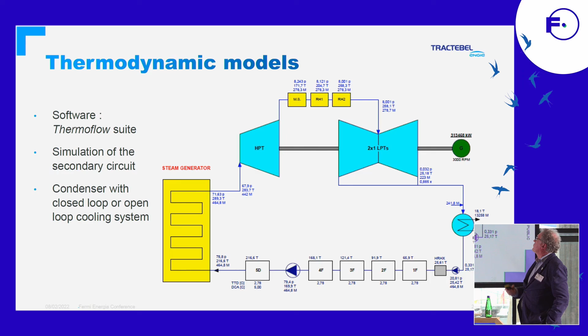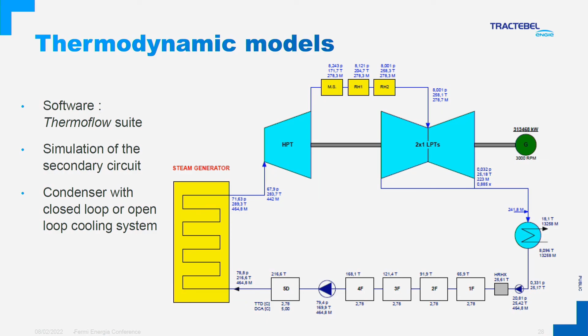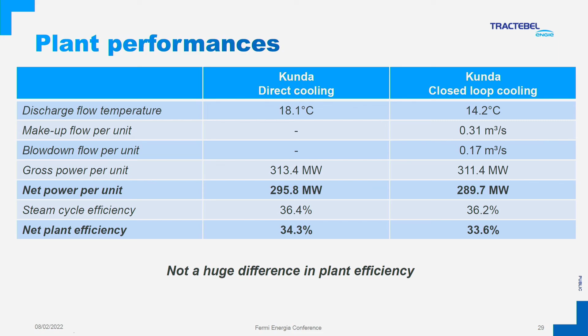So we did some thermodynamic modeling of the secondary circuit to calculate efficiency factors. This is the comparison, actually for two cases, Kunda direct cooling and Kunda closed-loop cooling, where we see the net power has a difference of 6 megawatts, about 2% of the power output. That's the penalty of applying closed-loop cooling. So it's not a huge difference in plant efficiency — 6 megawatts for 300 megawatts.